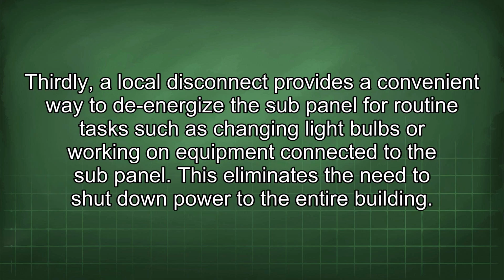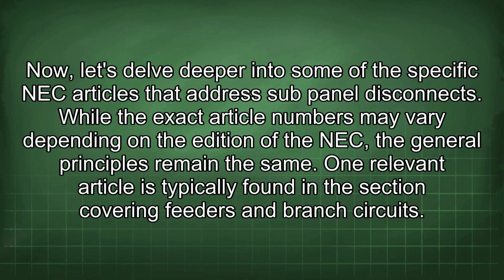Thirdly, a local disconnect provides a convenient way to de-energize a sub-panel for routine tasks such as changing light bulbs or working on equipment connected to the sub-panel. This eliminates the need to shut down power to the entire building. Now let's delve deeper into some of the specific NEC articles that address sub-panel disconnects. While the exact article numbers may vary depending on the edition of the NEC, the general principles remain the same.